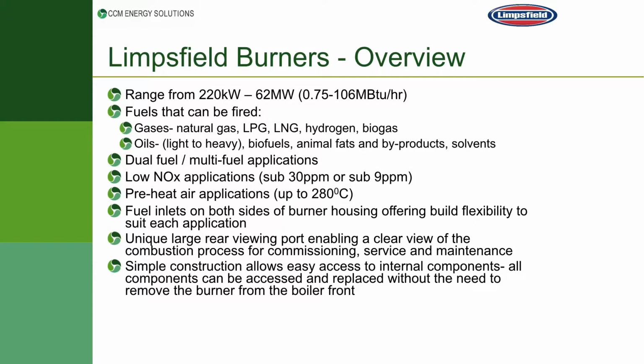As I said, for the range of these burners, they have a package burner that operates from 220 kilowatts through to 3 megawatts. And then outside of it, we move into the bespoke burners up to 62 megawatts. So that pretty much covers the majority of boiler applications here in Australia. The fuels that the burner can fire are gases and oils. So gases can be natural gas, LPG, LNG, hydrogen, or biogas.